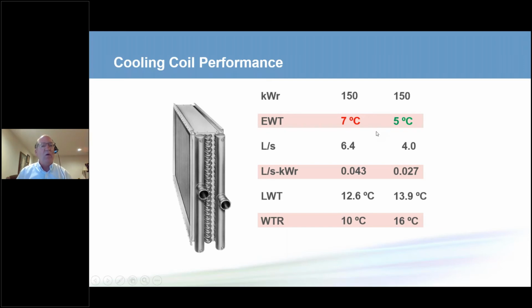Now, one question people ask is, when doesn't this work? Well, it may not work on small fan coils that have only 2 or 3 rows, because with those reduced rows, there's reduced heat transfer area, and therefore the return water temperature follows the supply water temperature down. But on almost all air handling coils that are 6 to 8 rows, particularly those that have internal enhancements, this works extremely well. And we've seen many jobs use new colder chilled water temperatures and reduce their pumping power significantly using the existing coils.